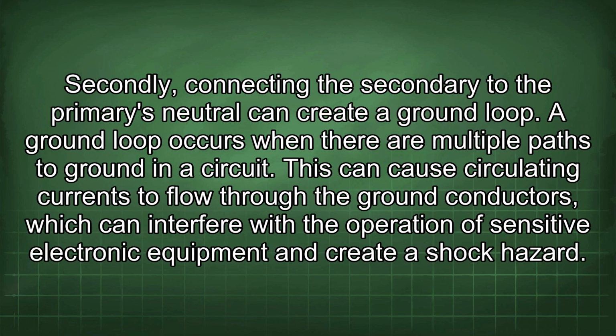Secondly, connecting the secondary to the primary's neutral can create a ground loop. A ground loop occurs when there are multiple paths to ground in a circuit. This can cause circulating currents to flow through the ground conductors, which can interfere with the operation of sensitive electronic equipment and create a shock hazard.